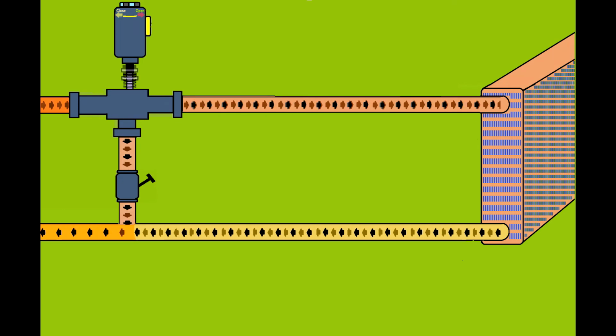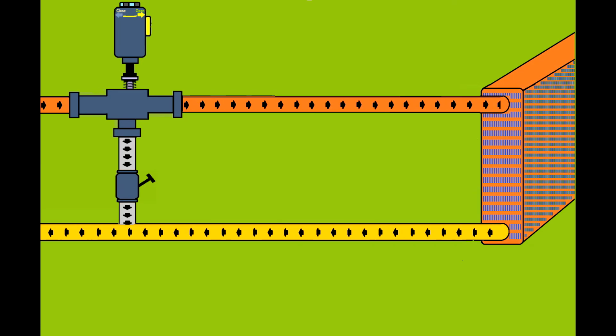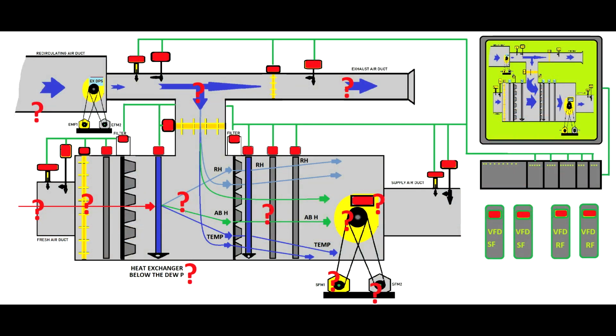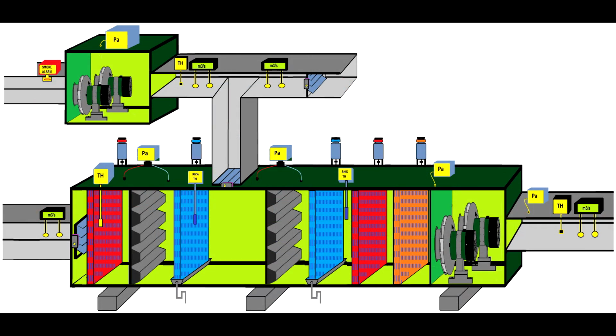This actuator is a three-way valve, control a three-way valve, and as you will see here, it's not 0 or nothing. It is PID, which allows more or less heating or cooling agent to pass by. When you design an air handling unit, you have to look at this. Everywhere you see a question mark, it's a place where you have to pay attention, not only on the control, but on the design.